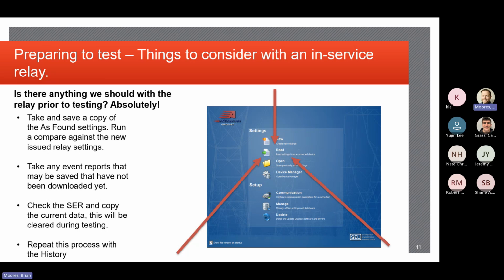Any event reports that are in the relay, just in case there was an event report triggered from an actual system fault that perhaps the client didn't get a chance to download, it's great to save those. The sequential events recorder, you can copy that data out as well. So what you're trying to do is establish a baseline: this is how I sat down and found this relay. You're basically covering yourself to say, I've saved these things, this is how I found it. You can either restore it, but you also have a record of what was there.